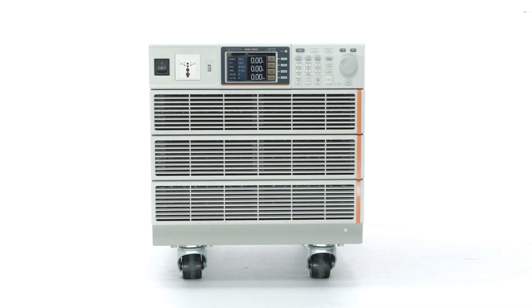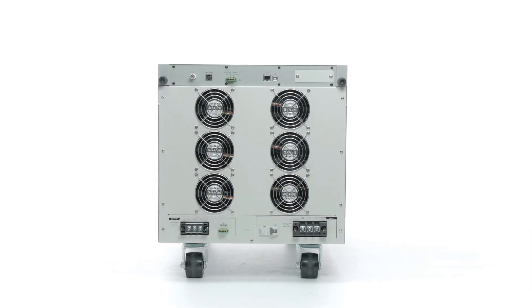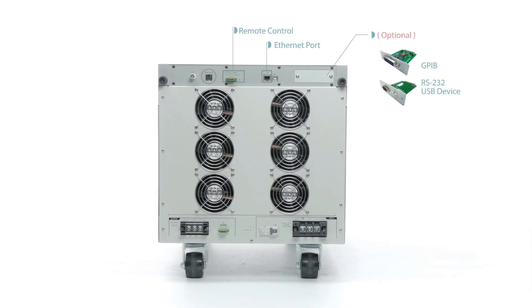Users can conveniently augment the output voltage from 0 volts to 600 volts RMS and output frequency from 45 Hz to 999.9 Hz by purchasing options without sending equipment back to GW INSTEK.